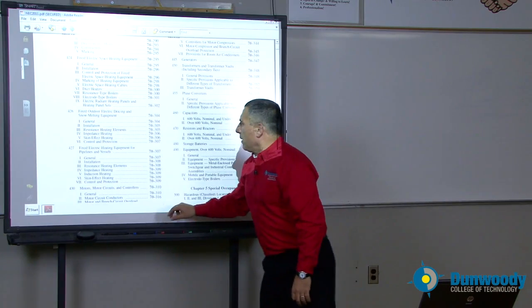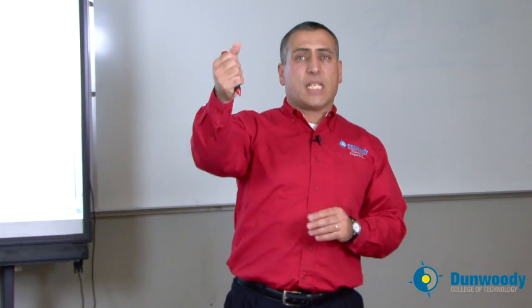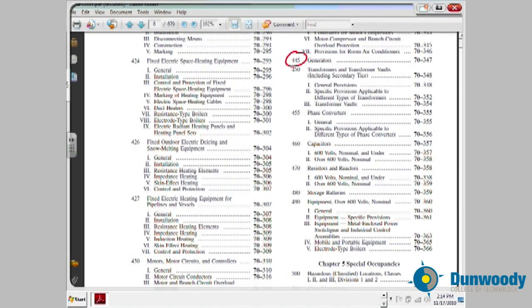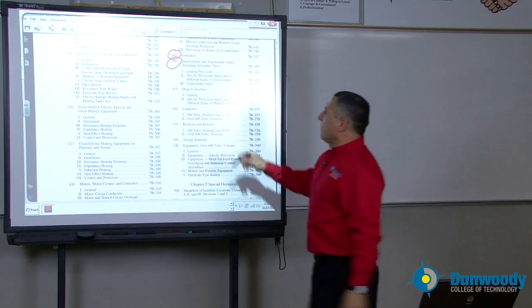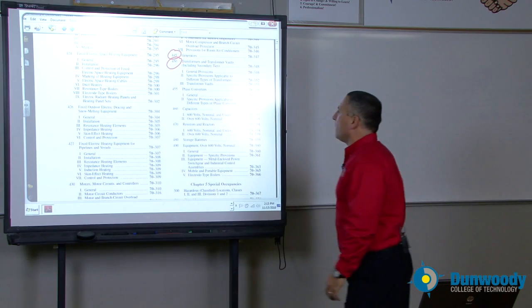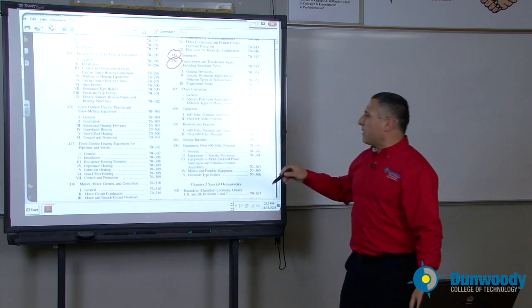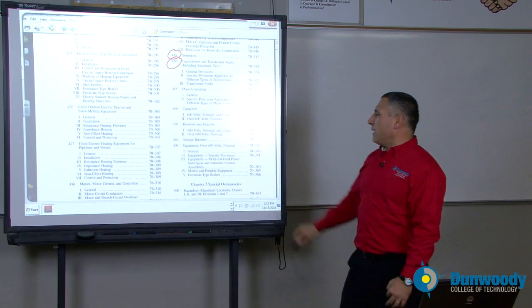Transformers and generators: if you have a generator, how do you size the overcurrent protection device and the conductor from the generator into the first overcurrent protection device? You'll find this in article 450. Every respected building in the industry is going to have a 480/277V system that steps down to 208/120V. How do you install this transformer? What's the largest transformer you can put in without a transformer vault? All this information is in article 450.